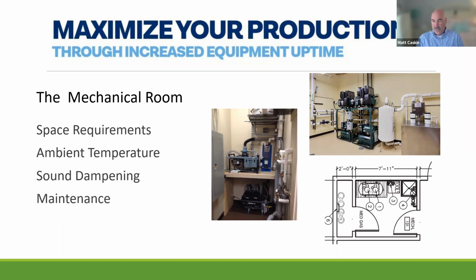The manufacturers will recommend certain space requirements. They'll give you dimensions of the actual equipment, but they're also going to give you space requirements as well. So for example, if an air compressor is 30 inches wide, they might require 33 or 34 inches. And if you're wondering why, it's because they've got to get airflow around this equipment. It does produce a lot of heat, and you want to make sure that you're giving it ample room so that the heat can dissipate and exit the equipment room. So we can go ahead and go to the next slide.